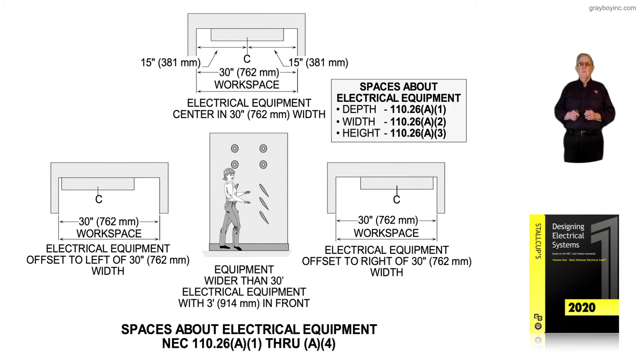Width — very important — that's NEC 110.26A2. Any time we approach a piece of equipment from the front to work on it, it should have at least a 30-inch width working space, or the width of the equipment, whichever is greater.